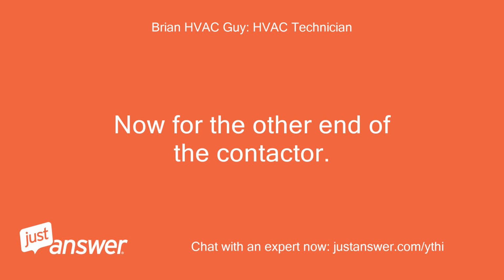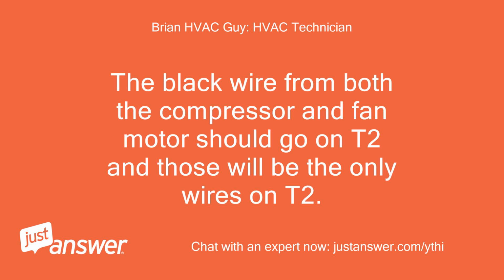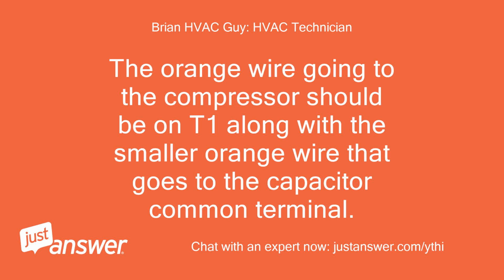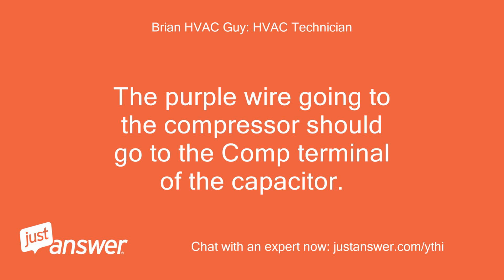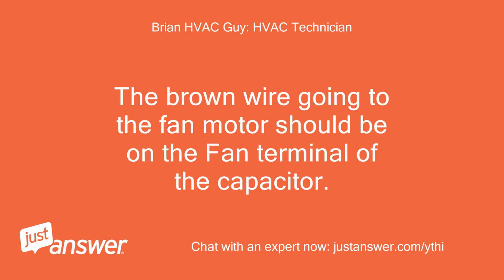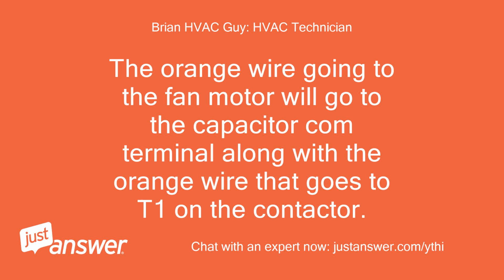Now for the other end of the contactor. The black wire from both the compressor and fan motor should go on T2, and those will be the only wires on T2. The orange wire going to the compressor should be on T1 along with the smaller orange wire that goes to the capacitor common terminal. The purple wire going to the compressor should go to the comp terminal of the capacitor. The brown wire going to the fan motor should be on the fan terminal of the capacitor. The orange wire going to the fan motor will go to the capacitor common terminal along with the orange wire that goes to T1 on the contactor.